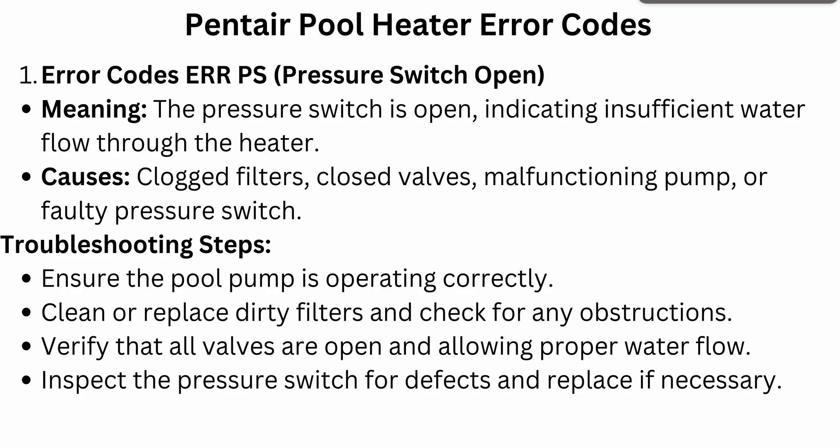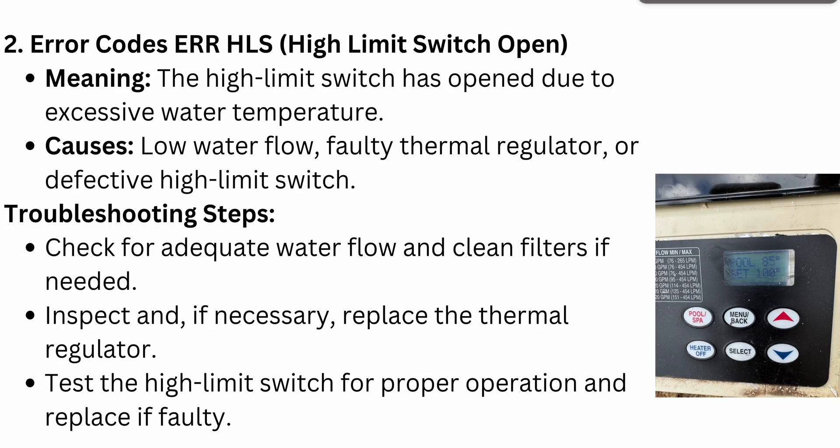Verify that all valves are open and allowing proper water flow, and inspect the pressure switch for defects and replace if necessary. Also, before checking any of these things when ERR pressure switch open is showing, make sure your heater is turned off. Do not inspect any part of your heater while it is connected to the power supply.